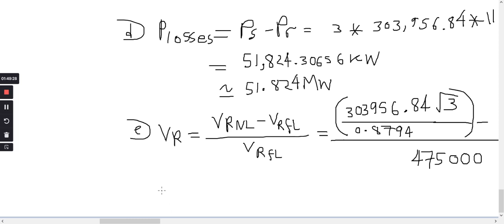0.8794. But remember that this is a phase value, so you got to multiply by root 3, minus the line value of the receiving end full load, which was 475,000. What is the next one? 303956.84 root 3 divided by 0.8794 minus 475000 divided by 475000. Gonna be 26%. 26% voltage regulation.